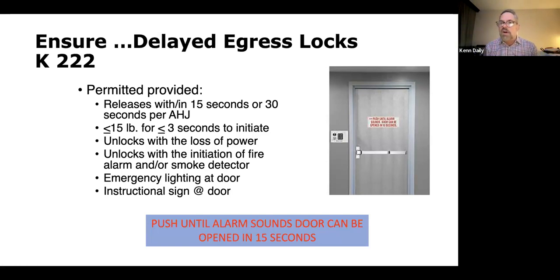And then you would hear that audible alarm sound, which then has initiated the unlocking process, which then, even with pressure off the panic bar, the door will open in 12 seconds after that 3 seconds. So roughly the whole operation takes 15 seconds or less. And of course, the doors lose this function altogether with the loss of power, the initiation of the sprinkler or fire alarm system. And as I showed you guys, that's a very common sight here in Pennsylvania.